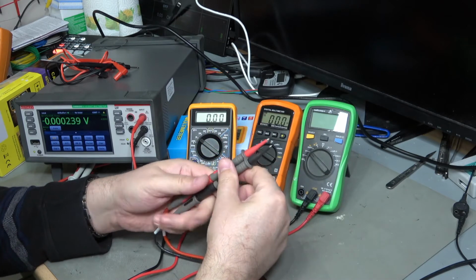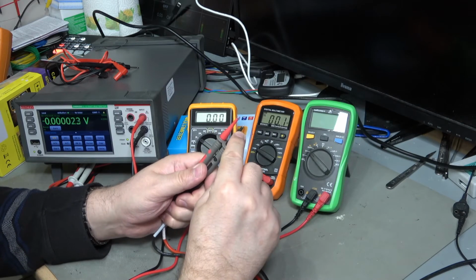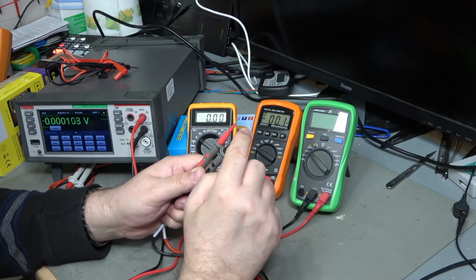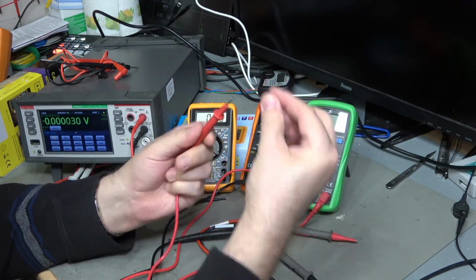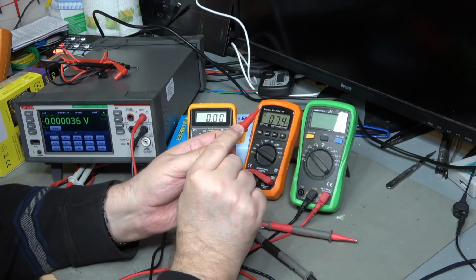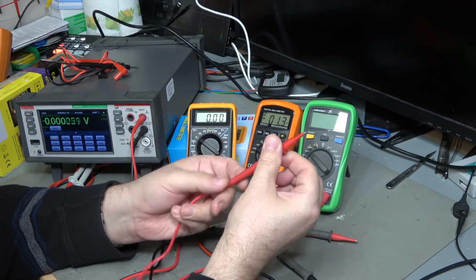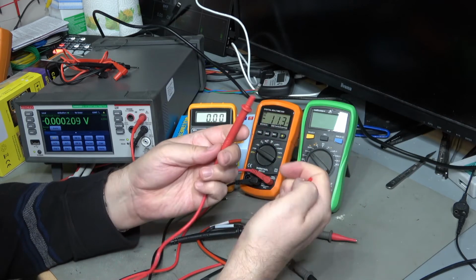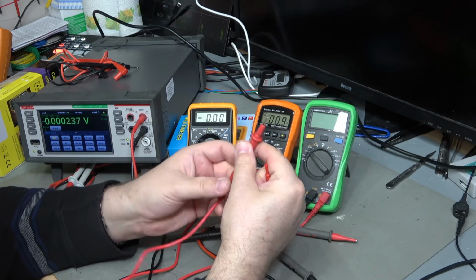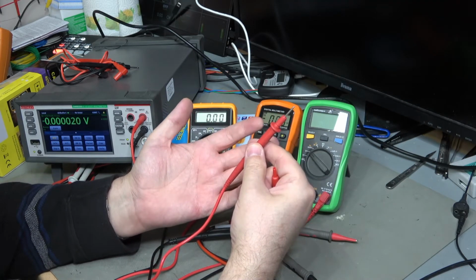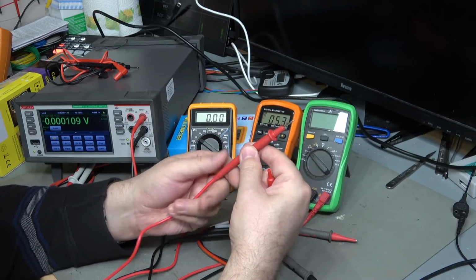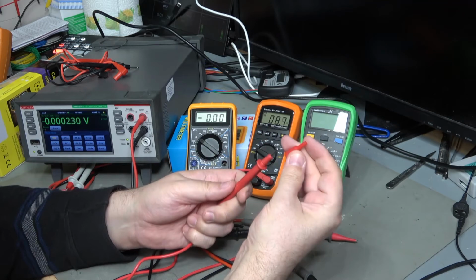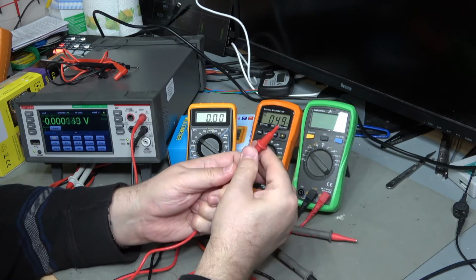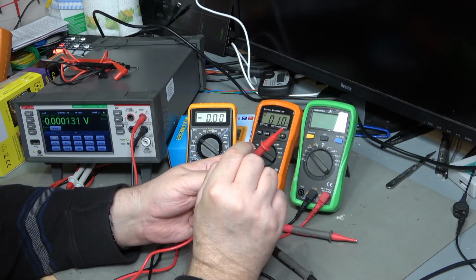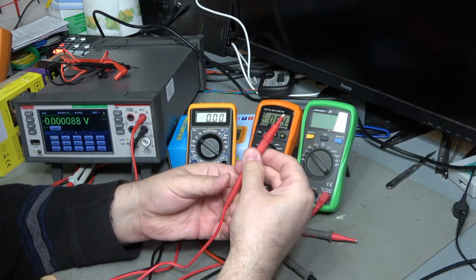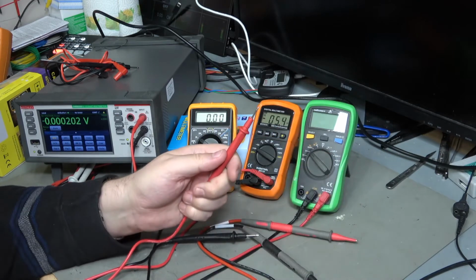They're quite nice. But notice the tip, it's all shrouded up to about 3 millimeters from the end. Let's say this guy. It's very common for them to come with a little clip on like this. So this is a 10 amp lead. Without that, it is Cat 2 only. So Cat 2 is simple, like domestic testing, that type of thing. If I put this on, boom, now it's Cat 3 1000 volts, Cat 4 600 volts. This is a 10 amp cable, which matches the 10 amps for the meter that it's attached to.